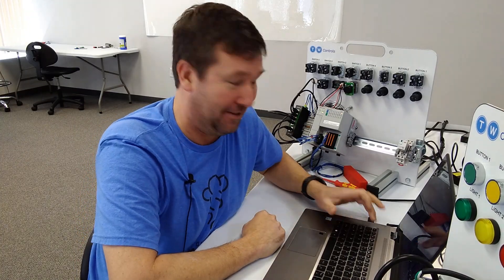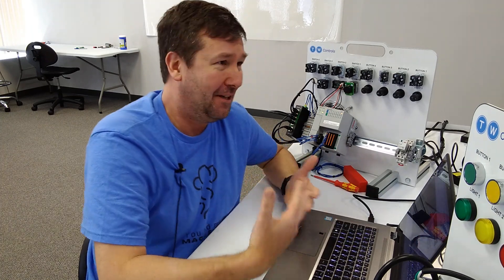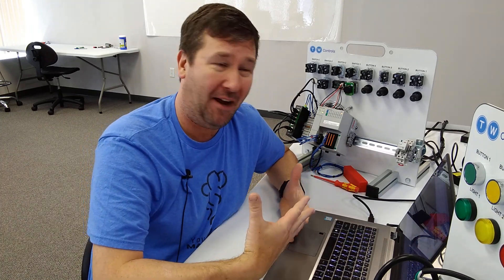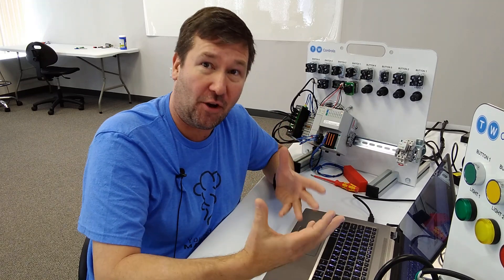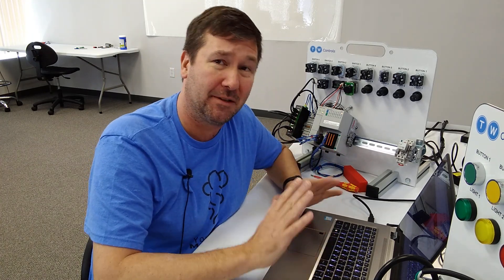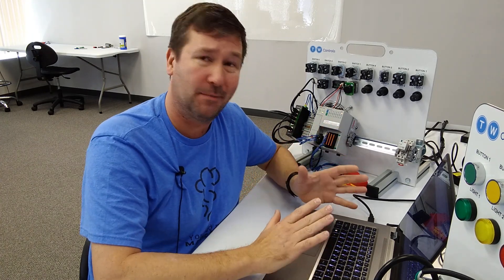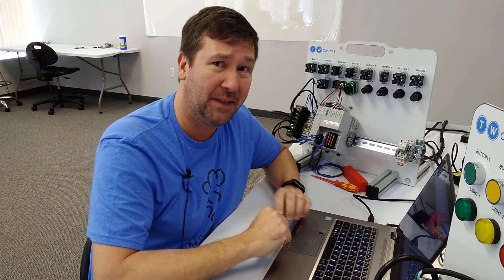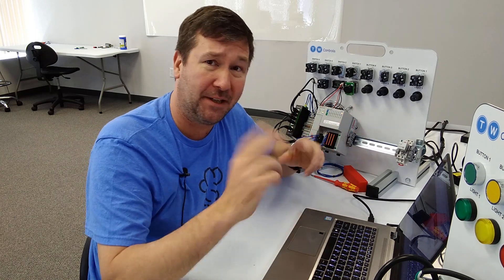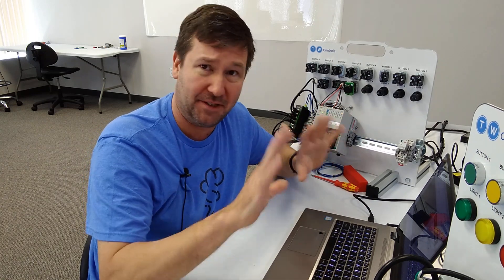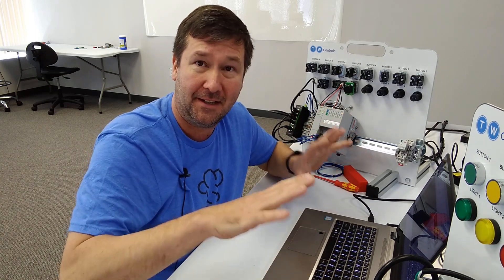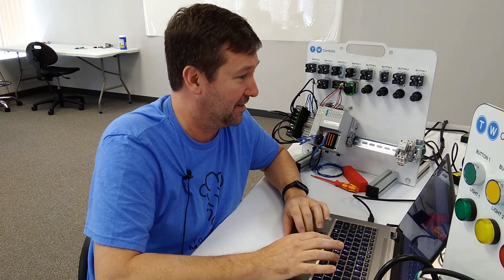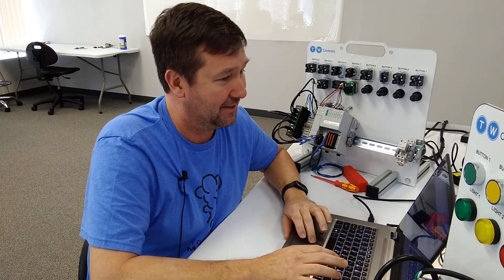I'll put a link to the rest of that video in the description, but I think you get the point. Really, if you have 15 horsepower worth of load that you need to run, then you need to get a 30 horsepower rotary phase converter. You're just going to be so much happier. I know it's a little more investment up front, but you'll be a lot happier. And I'll put a link in the description to the whole rotary phase converter video where you can learn more about what David is talking about.